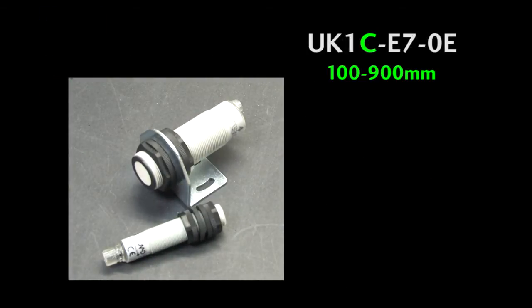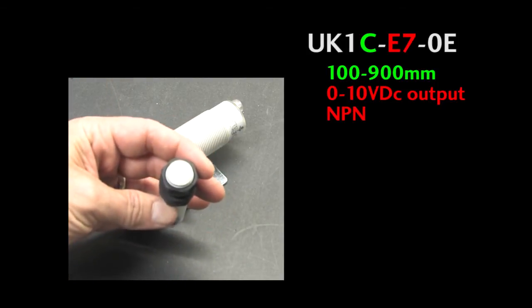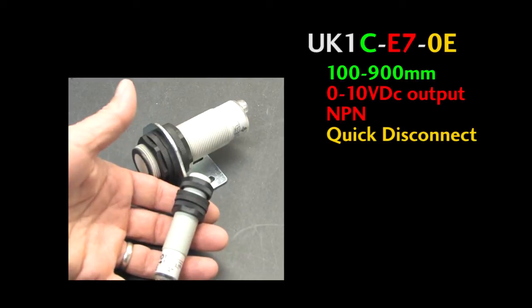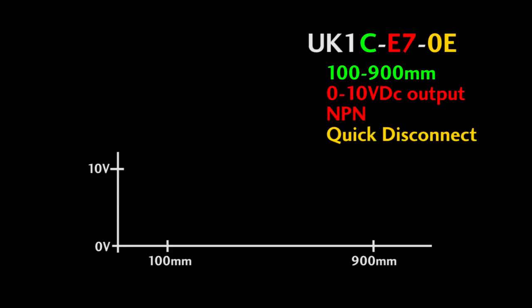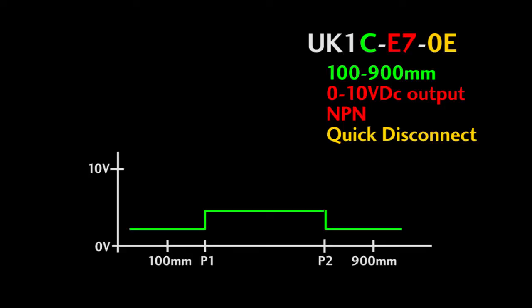I'm using this sensor which is a short range up to 900 millimeter sensor with an analog 0-10 volt output and an NPN output with a quick disconnect for the cable. This is a 100-900 millimeter sensor so we can set the detection range anywhere in here. That determines when the discrete output turns on and where the analog output starts and stops.